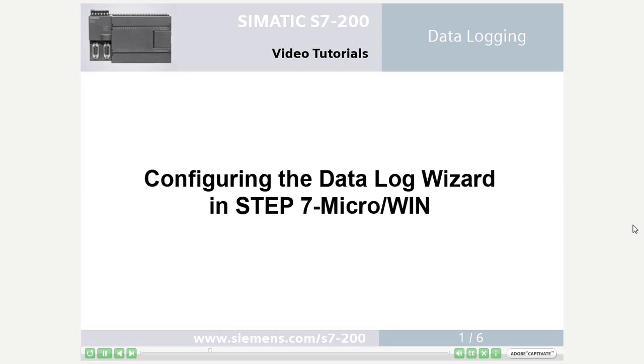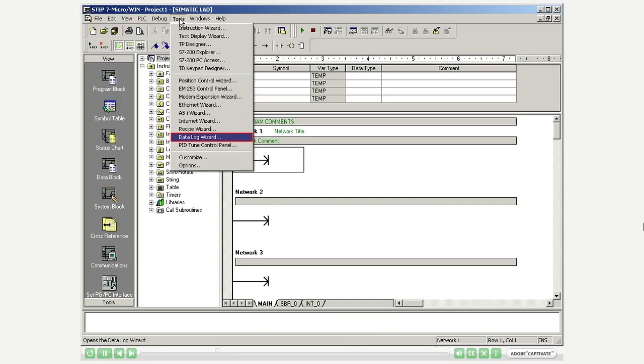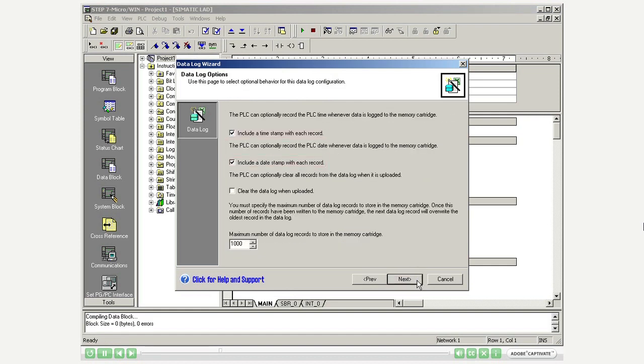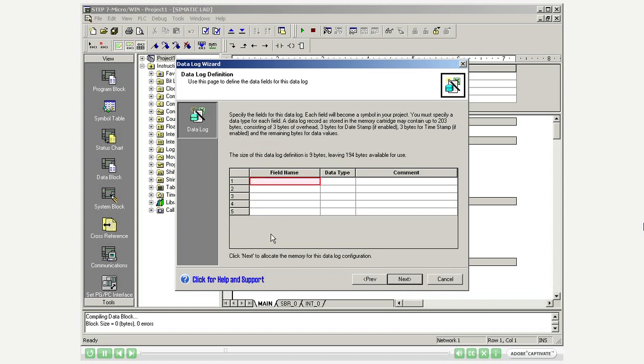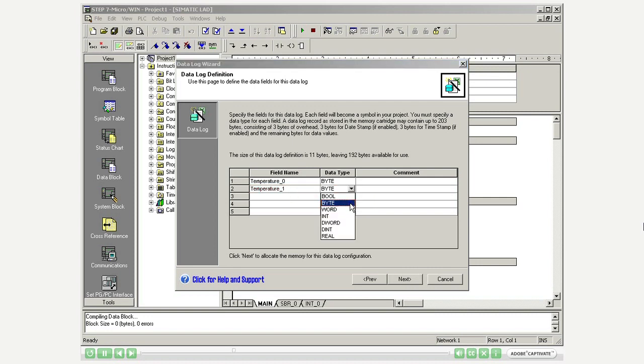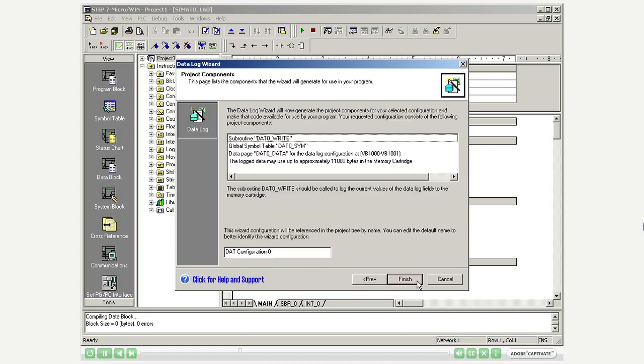Step 1: Configuring the Data Log wizard in Step 7 Microwin. Open the Data Log wizard. Select recording of the time and date stamp. Assign a name and data type that matches the values to be recorded. Select the start address of the memory area. Finish the Data Log wizard.